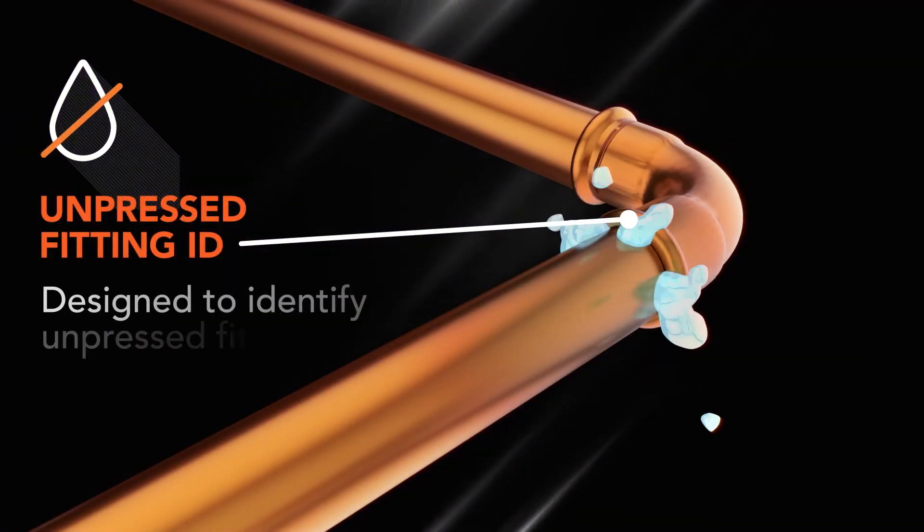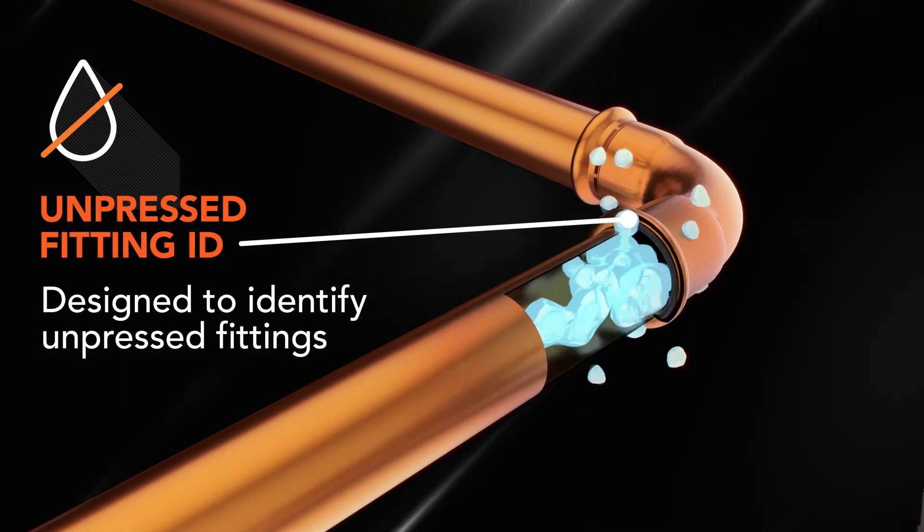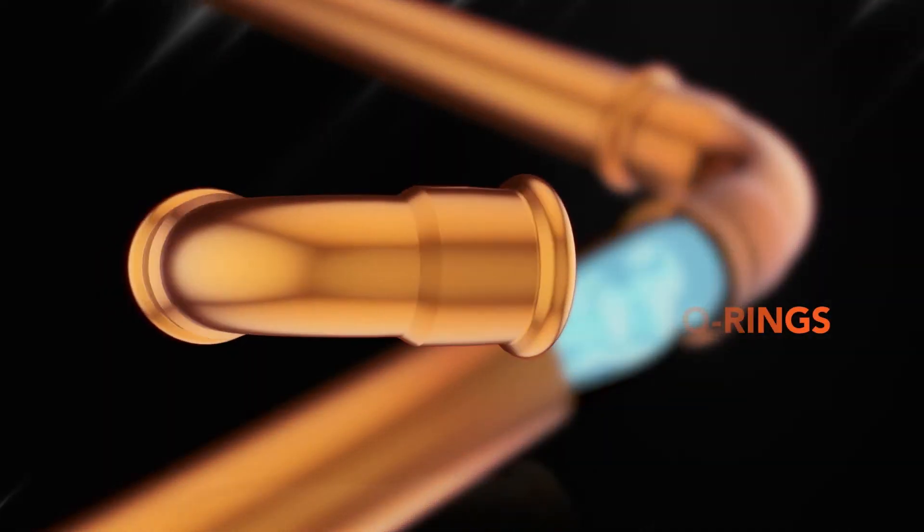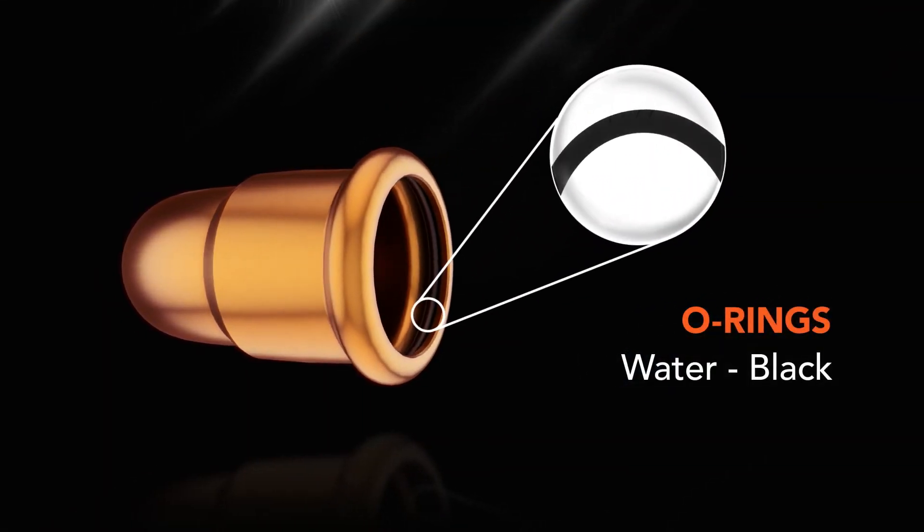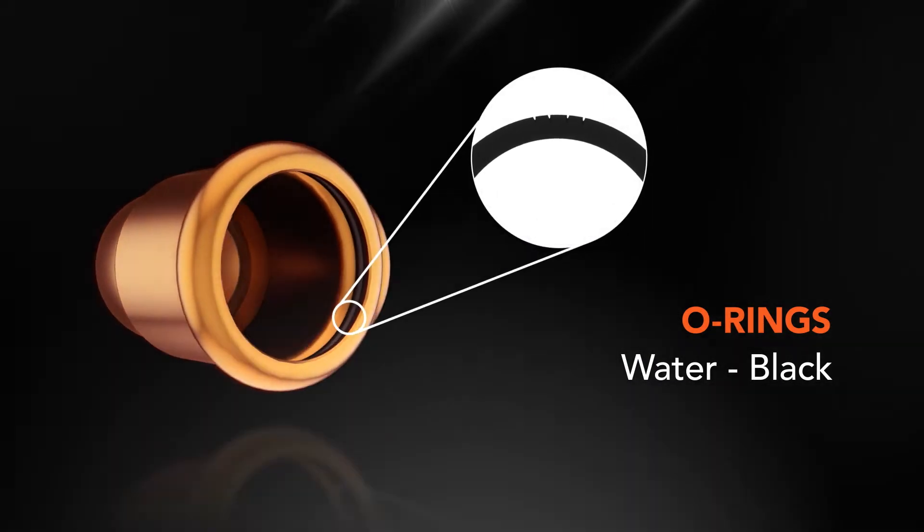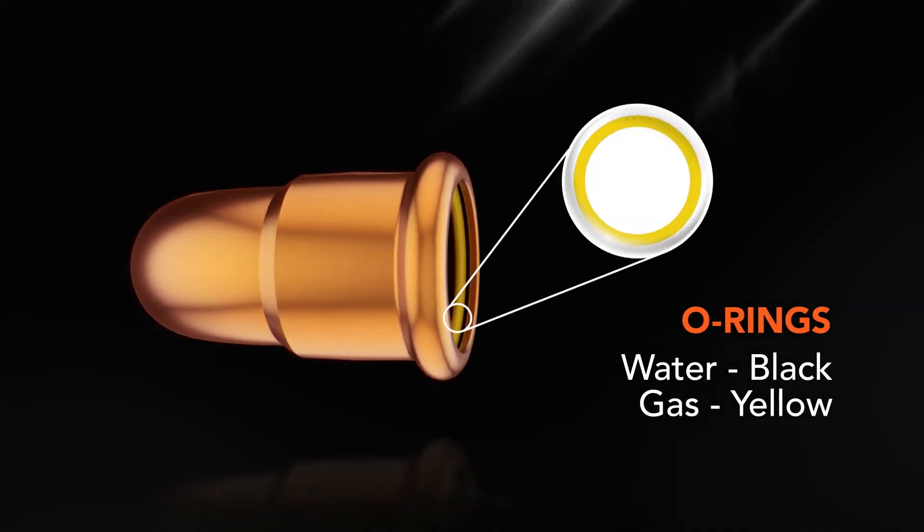The new unpressed fitting ID feature allows for water or air to escape from any unpressed fitting via a low pressure test, utilizing a combination of o-ring design and fitting tolerances to help you identify an unpressed fitting prior to commissioning.